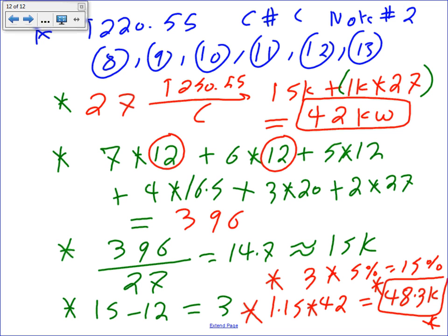We're done. We're going to add them up and size the feeder now. Any questions, guys? How we did them? The ones that I circled were less than 12. I have to make them 12 by code from note number 2. It says anything less than 12, that rule applies, please make it 12. So I have 48.3. The rest, I want to add all these steps, divide them by the voltage, size the cable, and size our protection device. I'm done.